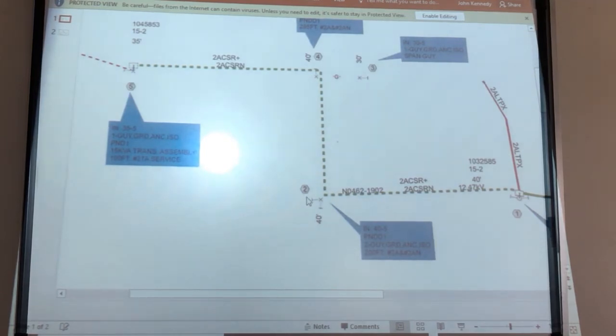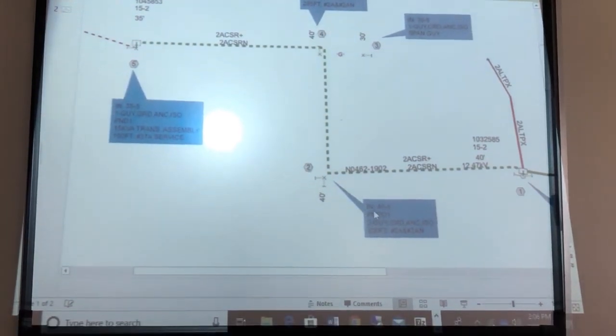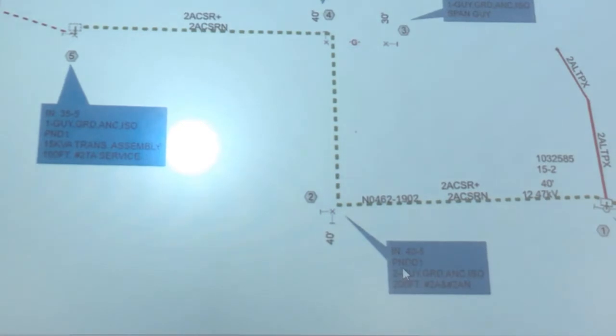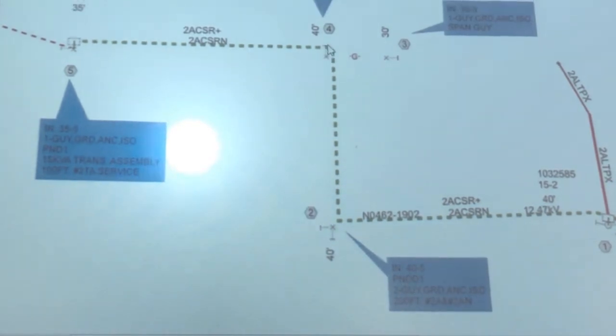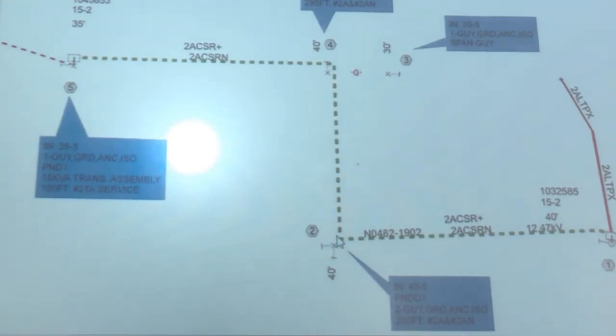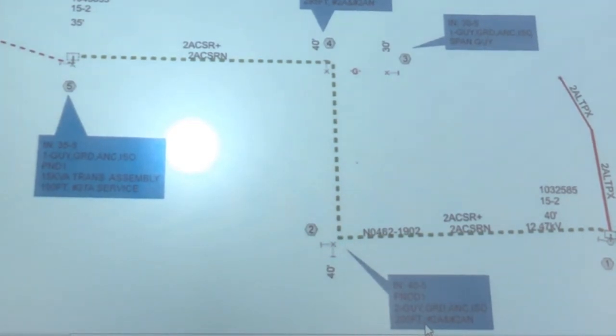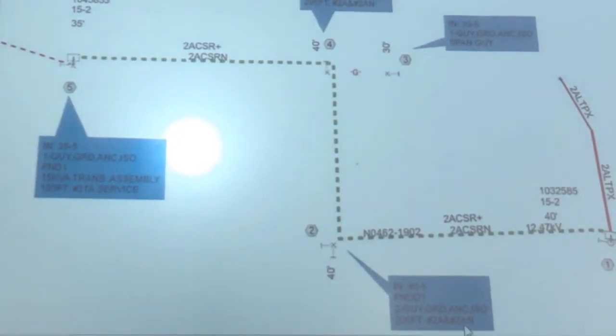At location 2 here, it indicates to install a 40-foot pole, and the class size is 5, a 40 class 5 pole. You're going to get the double dead end, same as on this pole here, and 200 feet of number 2 aluminum and number 2 aluminum neutral. Again, indicating your conductor from this pole to this pole is going to be 200 feet times 2.